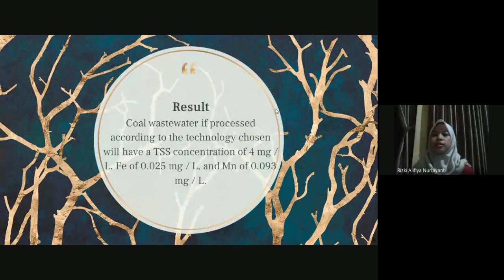So this is the result of the final project. Coal wastewater processed according to the chosen technology will have a total suspended solid or TSS concentration of 4 milligrams per liter, and then ferrum of 0.025 milligrams per liter, and then mangan of 0.093 milligrams per liter.